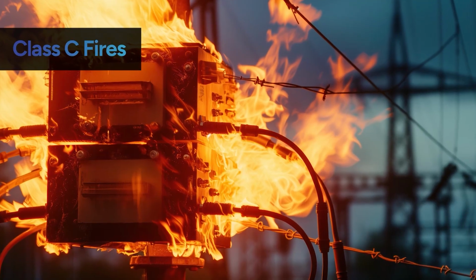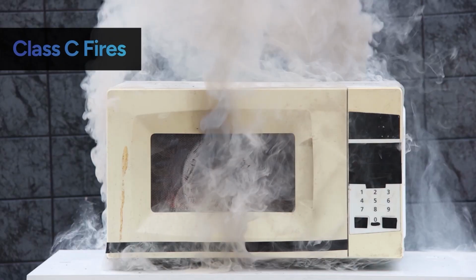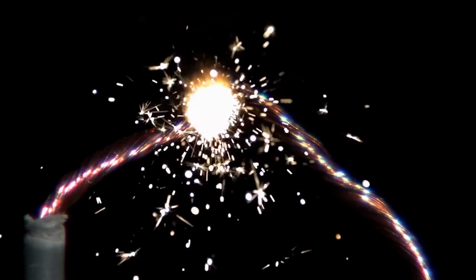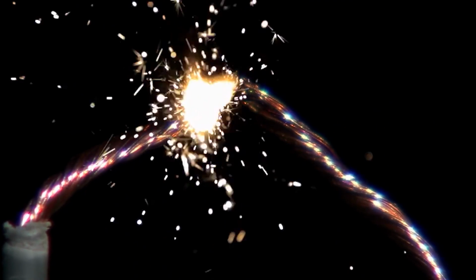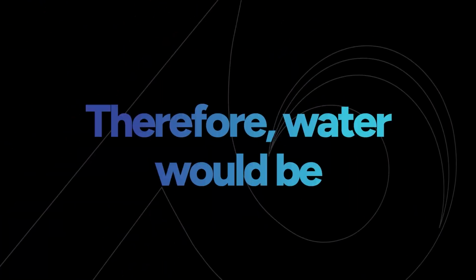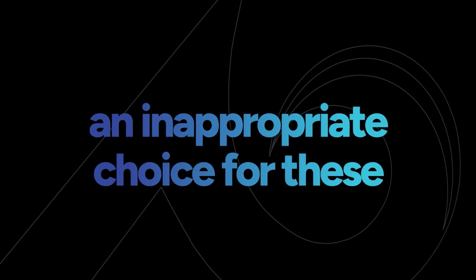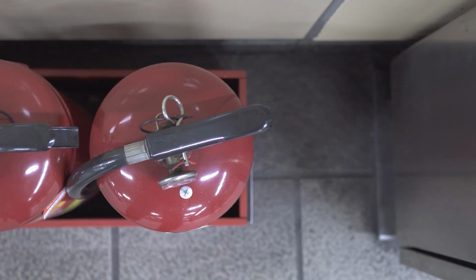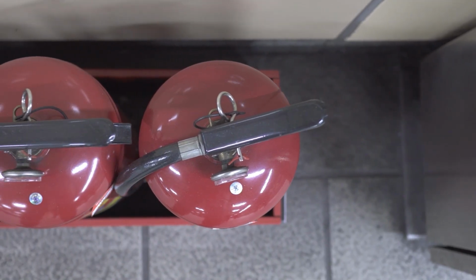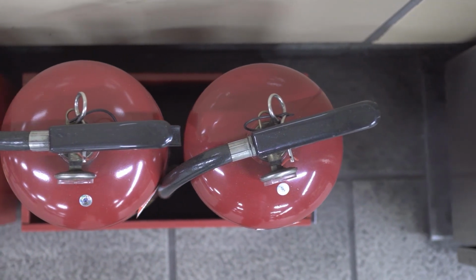Class C fires involve electrical equipment such as power systems, lighting, computers, and appliances. For Class C fires, it's important to use a fire extinguishing method that will not conduct electricity and create an electrocution risk. Therefore, water would be an inappropriate choice for these types of fires as well. Class C fires are best extinguished with dry chemical, CO2, or clean agent suppression.